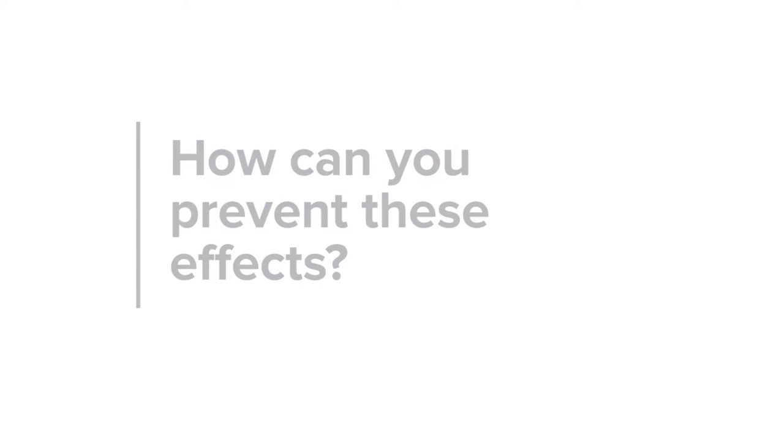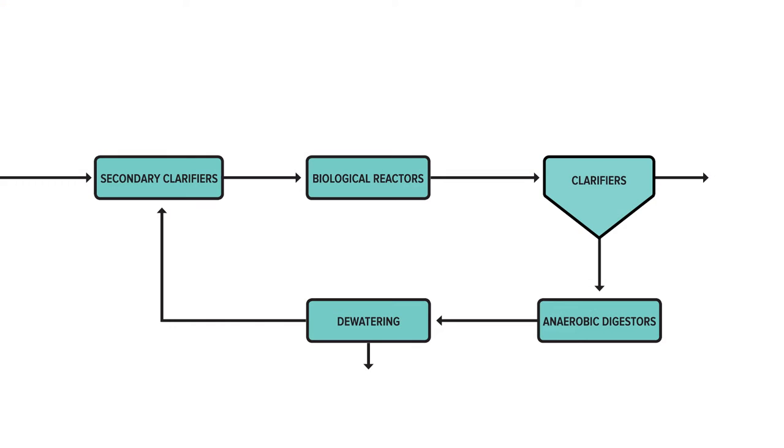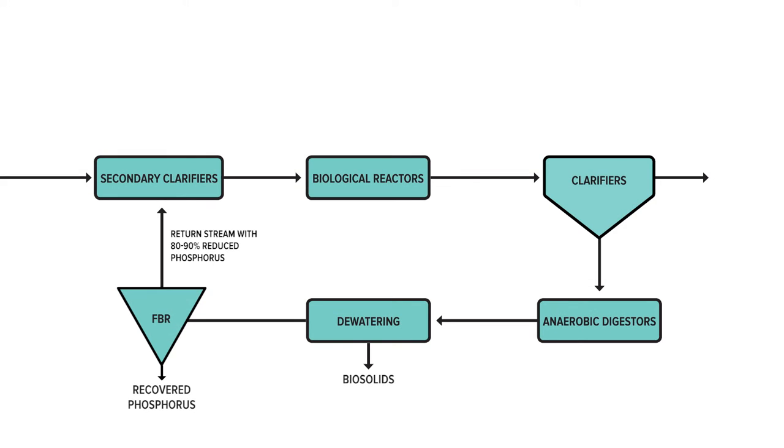One way to stop this racetrack effect is to intercept the side stream — that return stream — and recover the phosphorus. Typically it's going to be in the centrate or the filtrate. Using these technologies, the typical recovery rates can be in the 80 to 90 percent range, so they can really significantly reduce the loading coming back in the return stream.